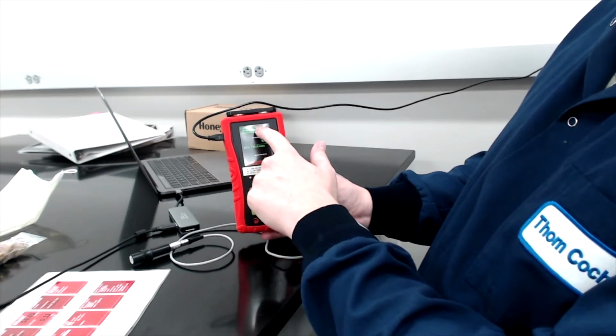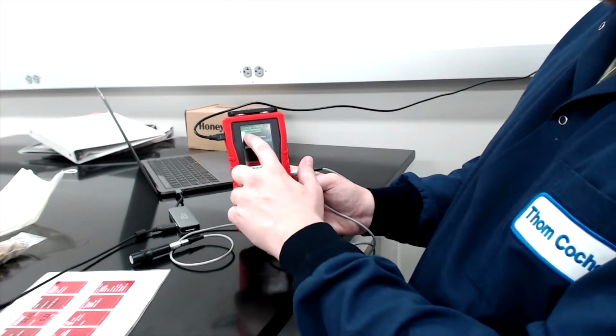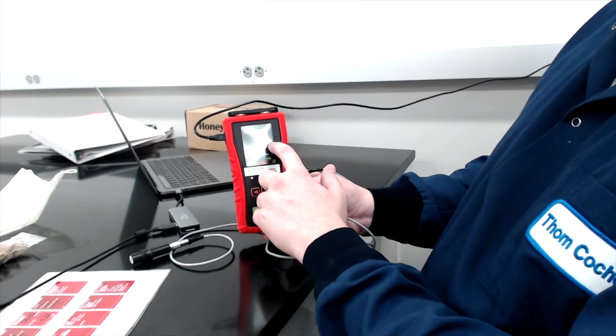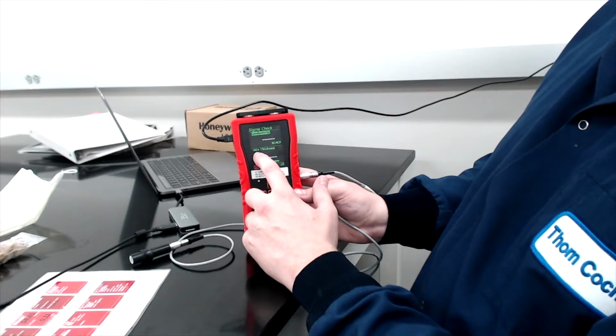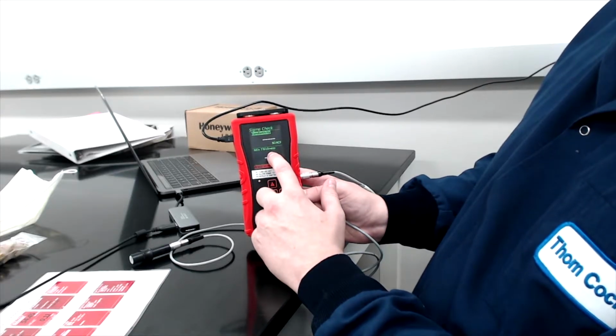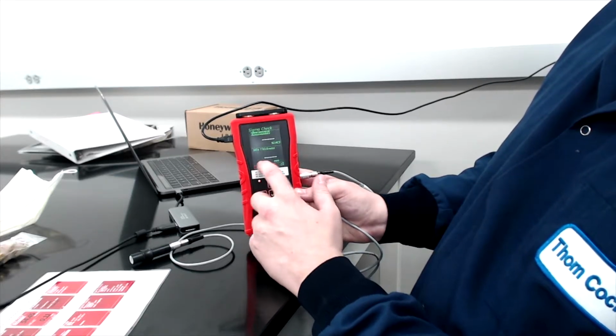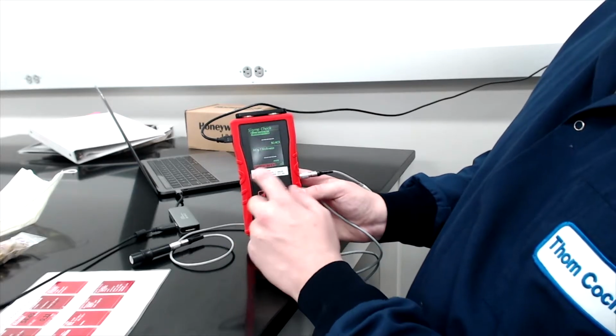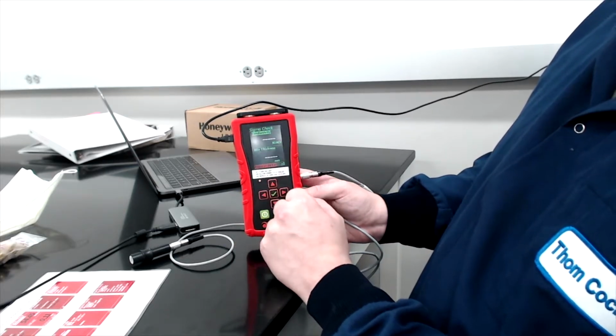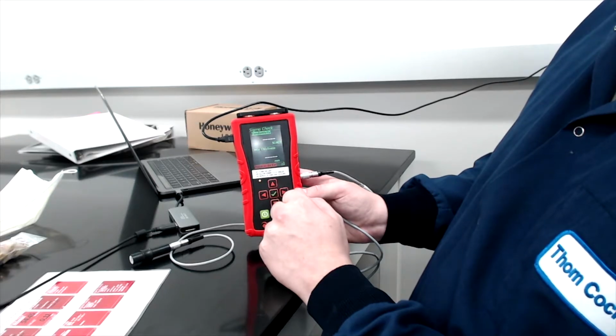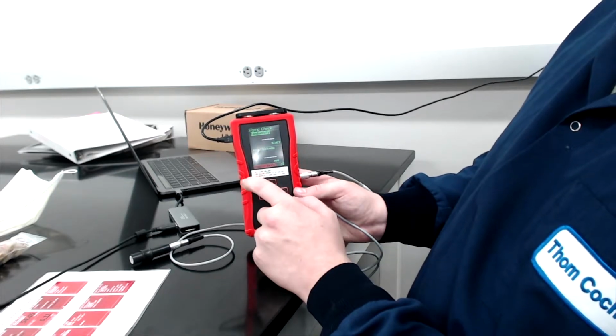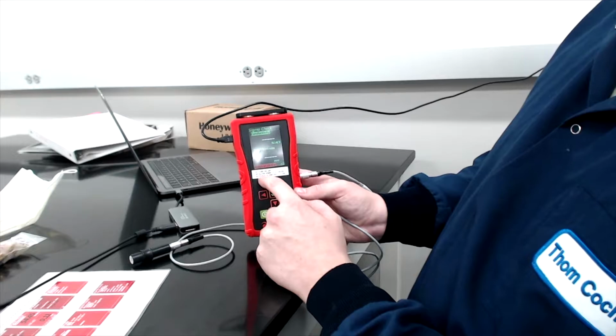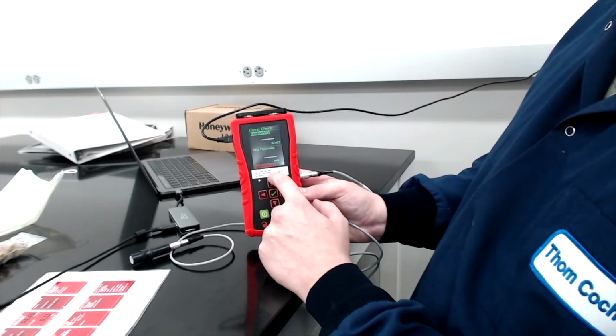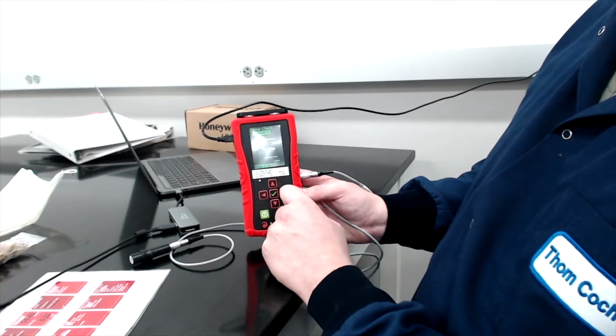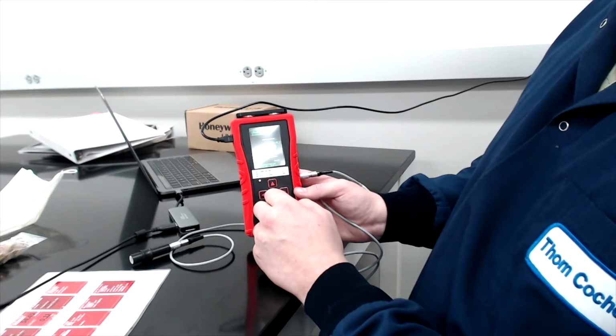It says SigmaCheck up here. Conductivity, it gives you the units here, and then down here there's options to change this, but for now it's going to be minimum thickness, and again the units. There's no readings because we are not using the probe yet, but we've turned this on, and the second step is actually to wait. So we're going to allow this thing to stabilize for 20 minutes.